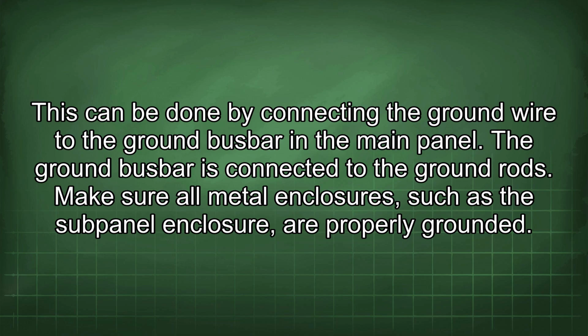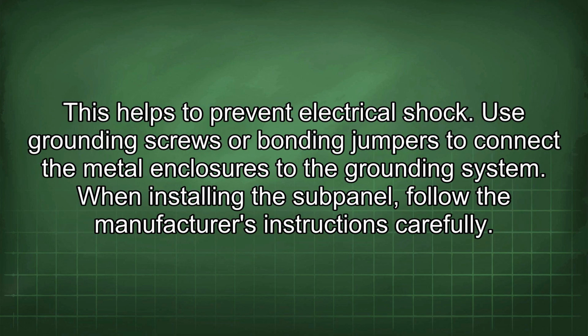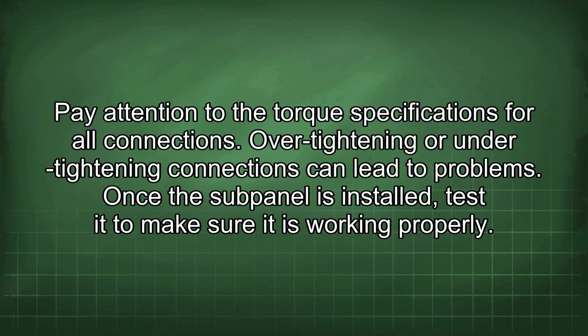Make sure all metal enclosures, such as the subpanel enclosure, are properly grounded. This helps to prevent electrical shock. Use grounding screws or bonding jumpers to connect the metal enclosures to the grounding system. When installing the subpanel, follow the manufacturer's instructions carefully. Pay attention to the torque specifications for all connections. Over-tightening or under-tightening connections can lead to problems.